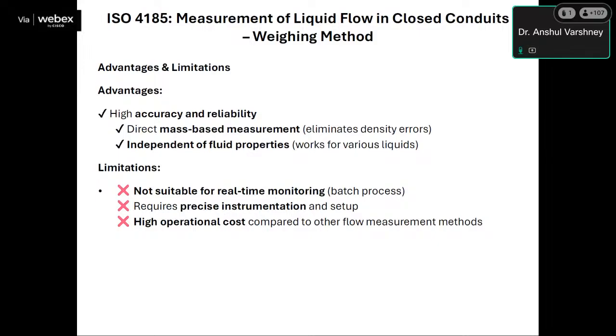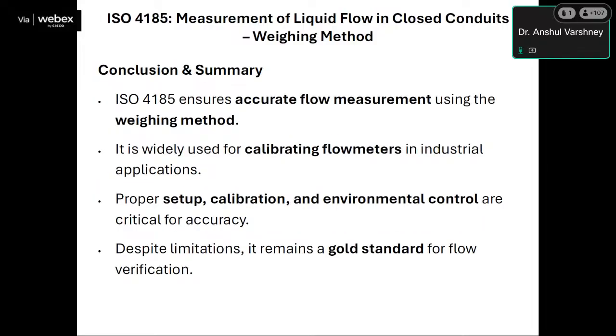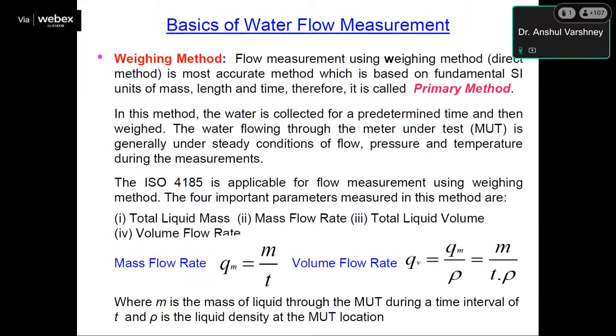And it is not suitable for real-time monitoring. It requires a precise instrumentation setup and has high operational costs compared to other flow measurement methods. The conclusion is that ISO 4185 ensures accurate flow measurement using the weighing method. It is widely used for calibrating flow meters in industrial applications. A proper setup, calibration, and environmental control are critical for accuracy. Despite limitations, it remains a gold standard for flow verification.